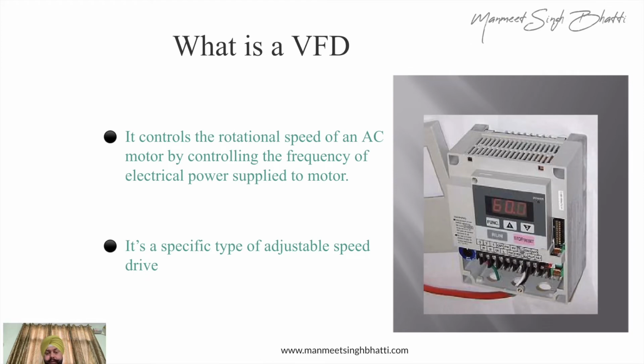Now, what is a VFD? As I have already explained, a motor is basically providing rotational energy. So it is rotating based on the power given to it. And the VFD controls the frequency of the complete power which has been given. Normally in India, the power frequency is 50 hertz, with a voltage of say 400 volt. You will have a standard RPM of the motor, like a 1440 RPM motor. So it will be rotating at the same speed.